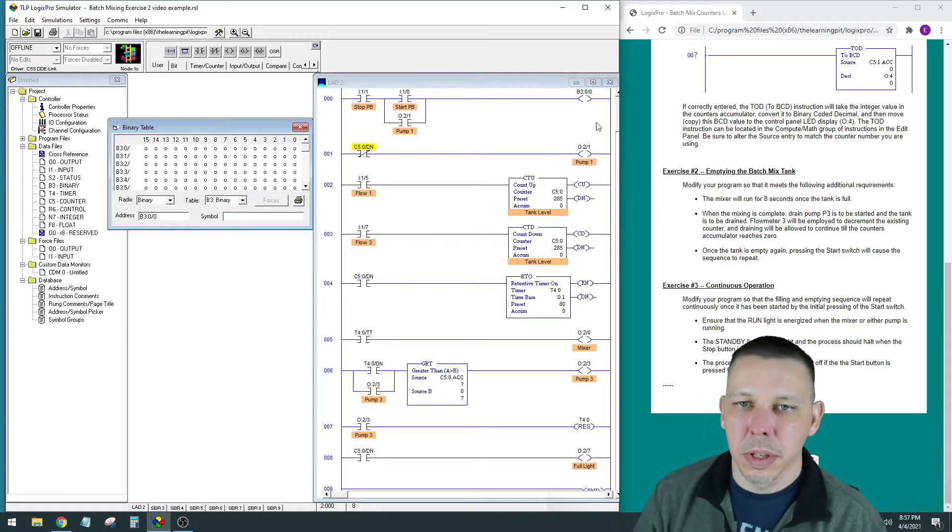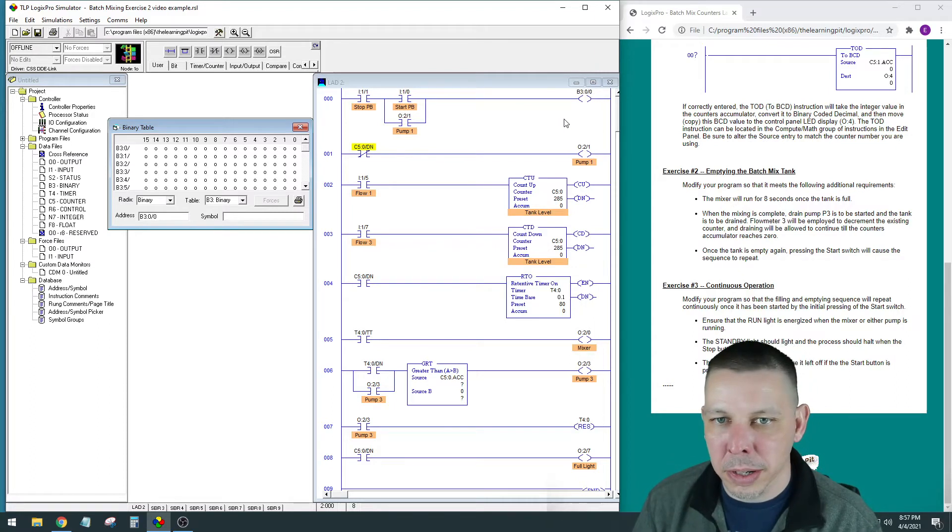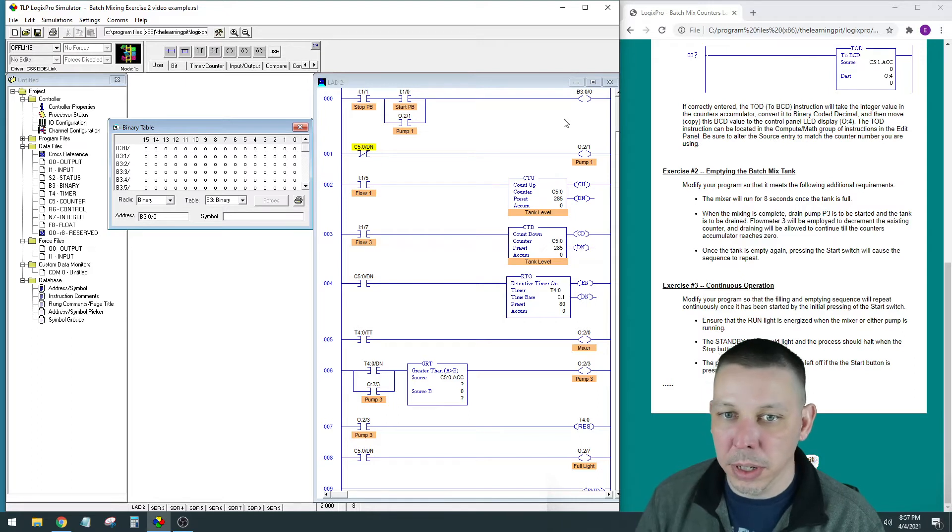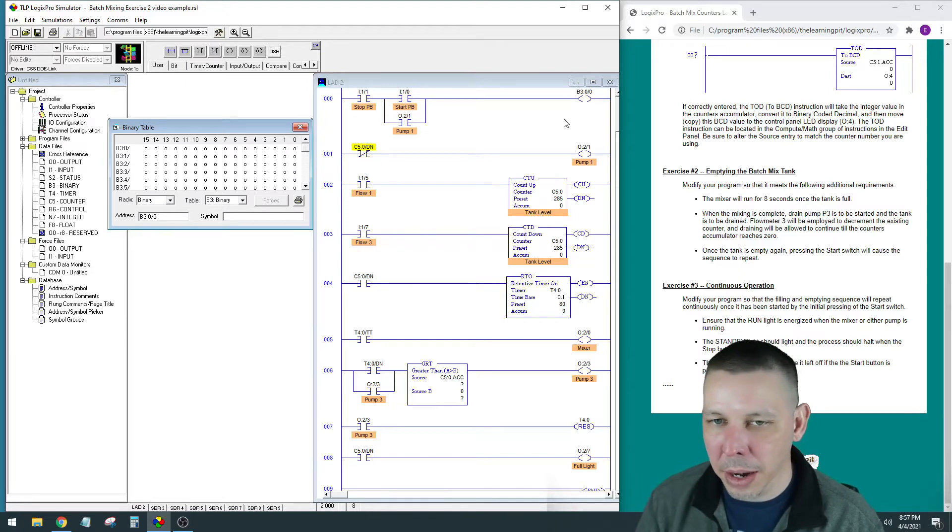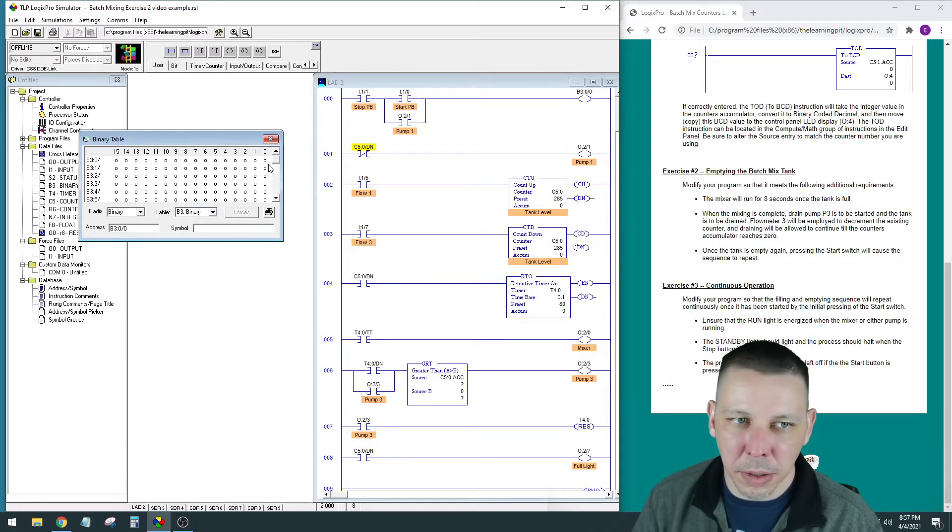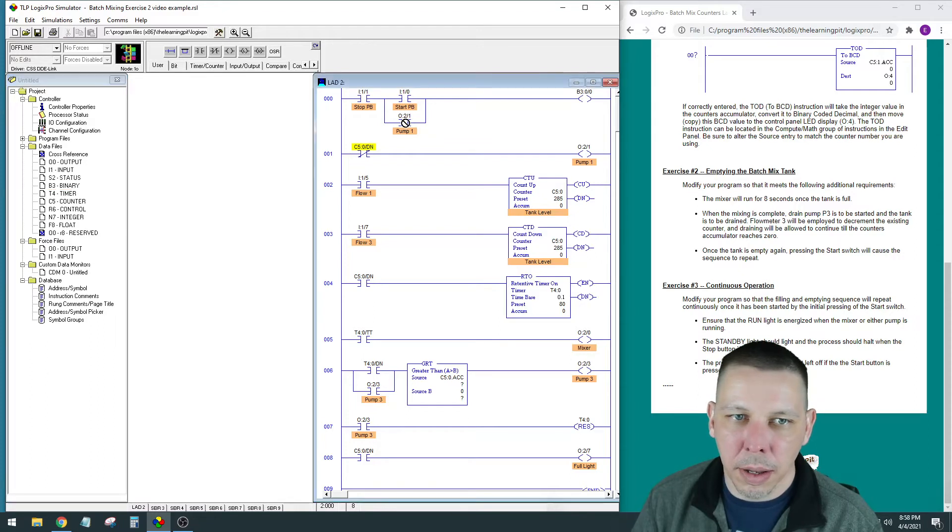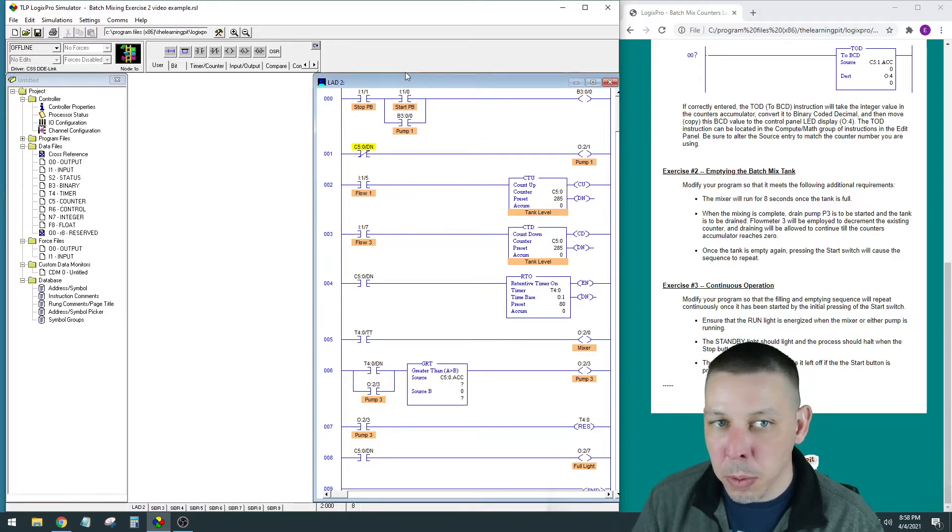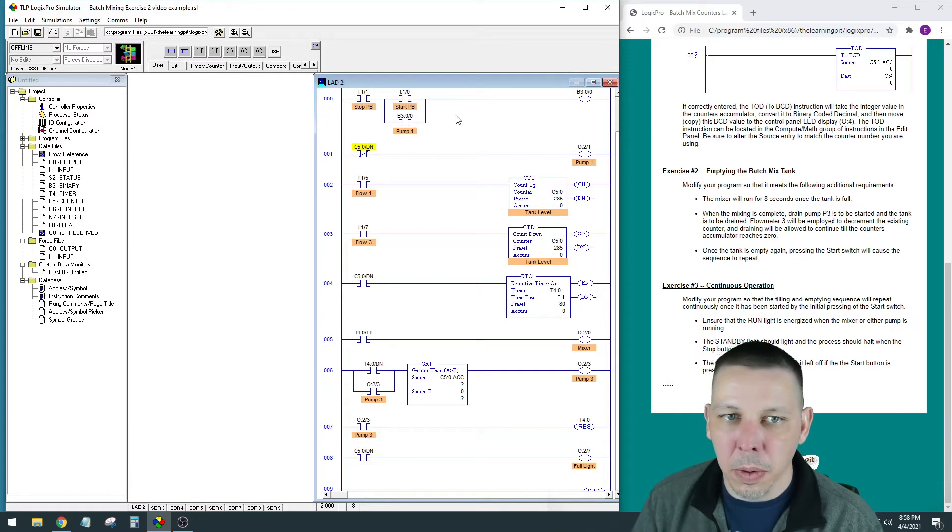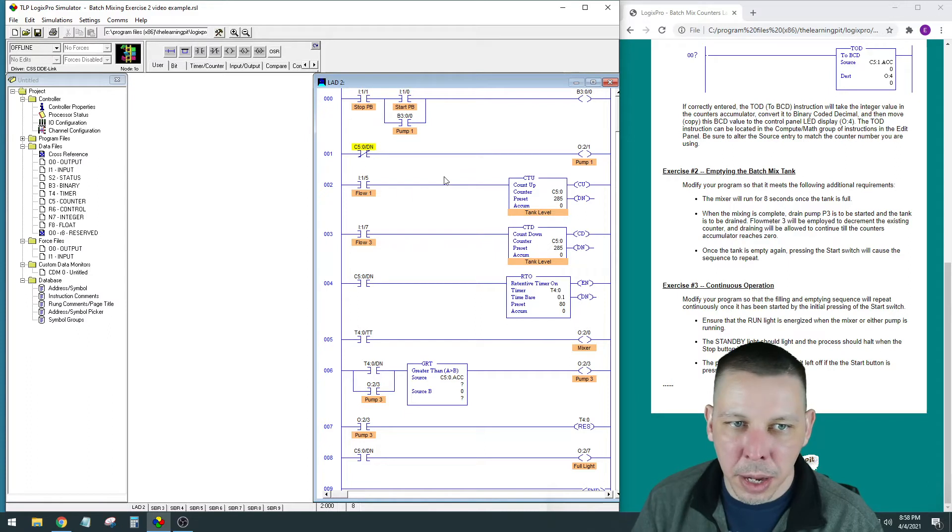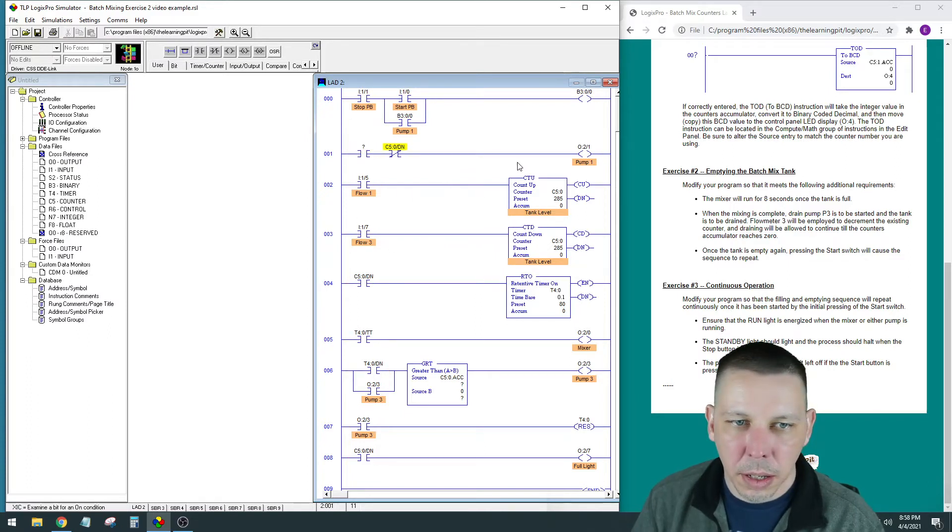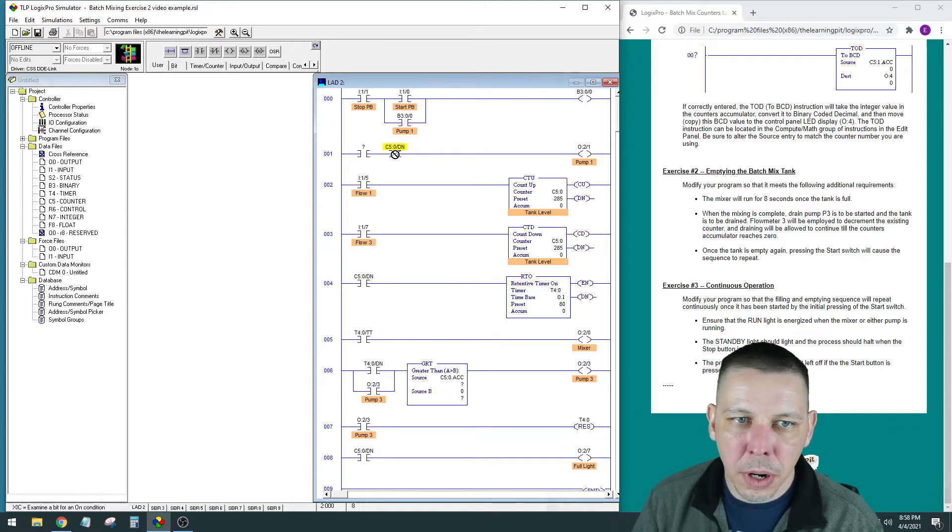Bit meaning binary digit—it's either zero or one, and it's just there for you using memory. I want the lowest one, which should be B3:0/0. So this looks just like an output except it's all internal of the processor. It's not physically flipping a relay or turning on voltage coming out of that processor—it's literally just a one or a zero in the memory at a location that you can address yourself. I'm going to have that and I'm going to have that latch itself in. So when I press this momentary start push button, this will go high and it'll latch around that start push button. The stop push button will be the same as we had it.